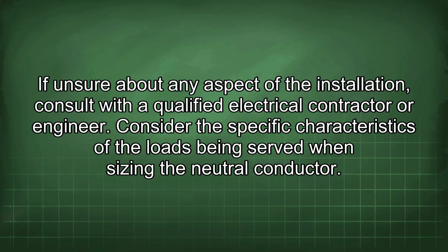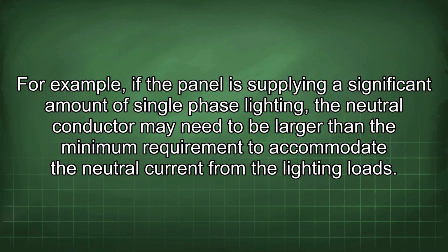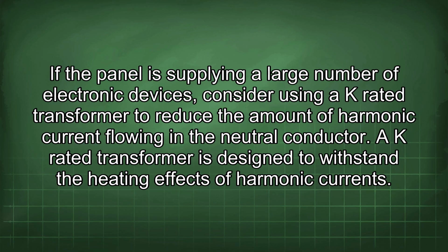Consider the specific characteristics of the loads being served when sizing the neutral conductor. For example, if the panel is supplying a significant amount of single-phase lighting, the neutral conductor may need to be larger than the minimum requirement to accommodate the neutral current from the lighting loads. If the panel is supplying a large number of electronic devices, consider using a K-rated transformer to reduce the amount of harmonic current flowing in the neutral conductor. A K-rated transformer is designed to withstand the heating effects of harmonic currents.